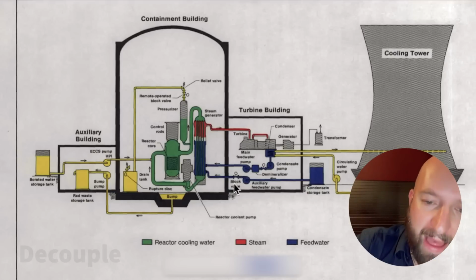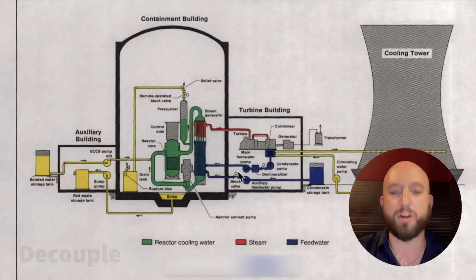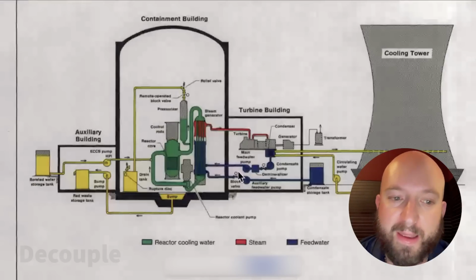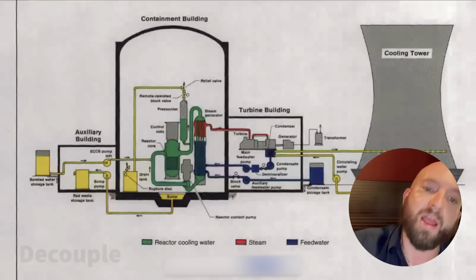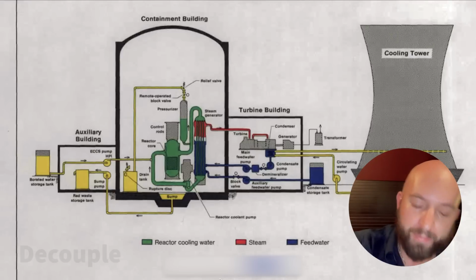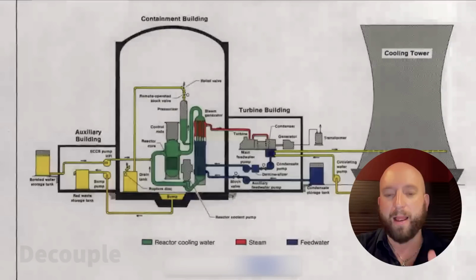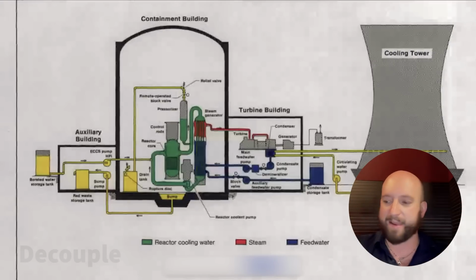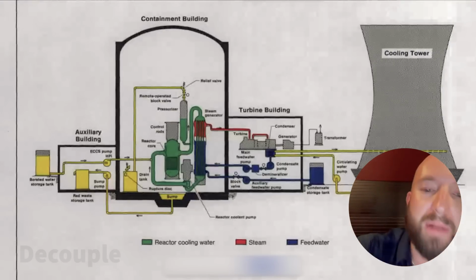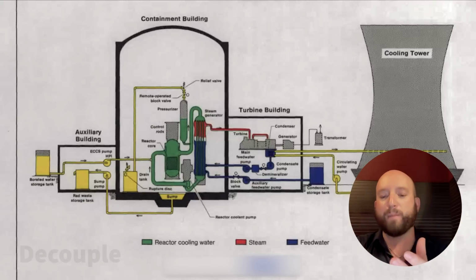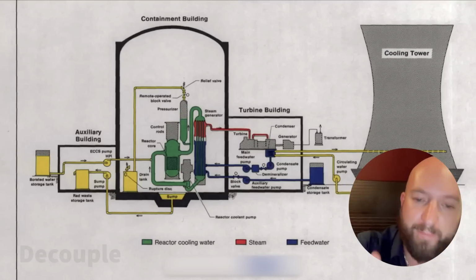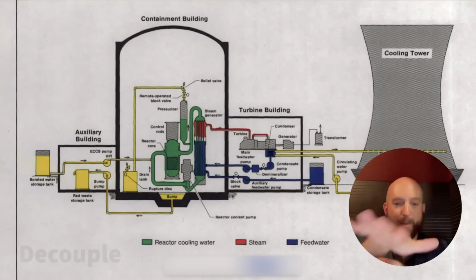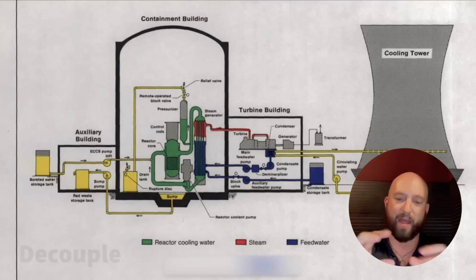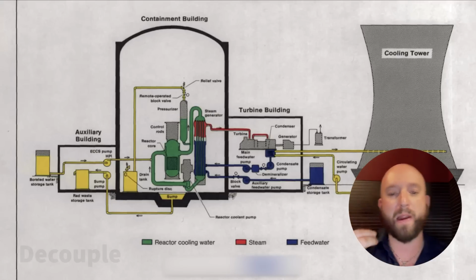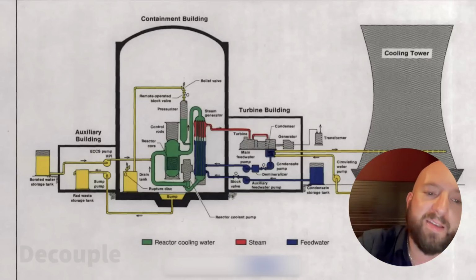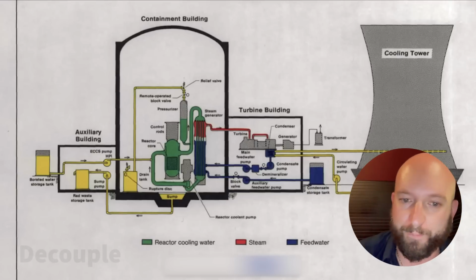There was a block valve here that had been shut a couple of days earlier for maintenance activities. Even though it was against plant procedure, those block valves remained shut. And it turns out that in the control room, even though there were lights indicating that these block valves were closed, those indicator lights were literally covered by paper tags indicating that a certain system was under maintenance. So the operators, when glancing at this, couldn't easily detect that those block valves were shut.